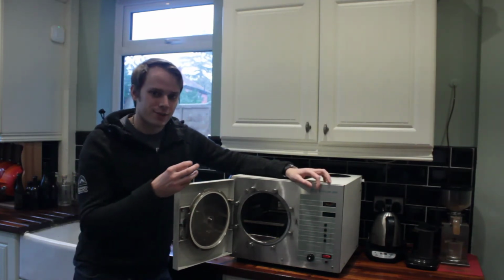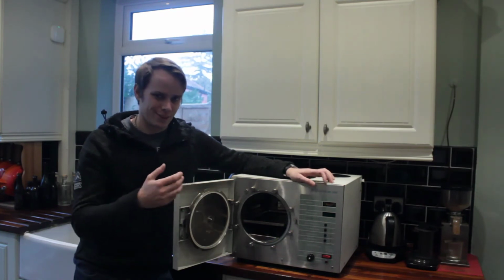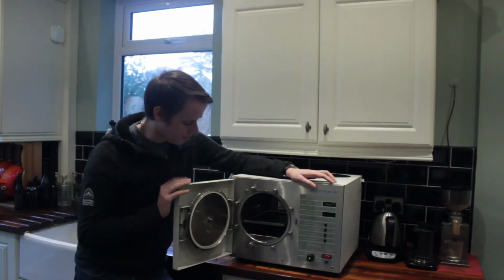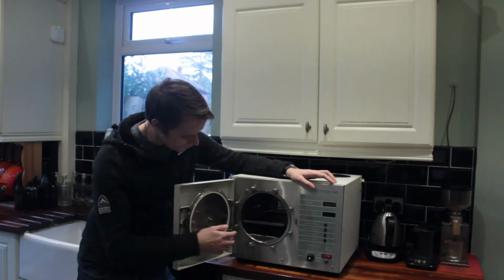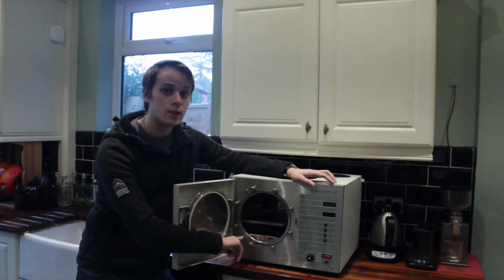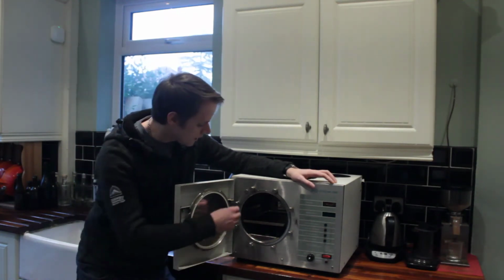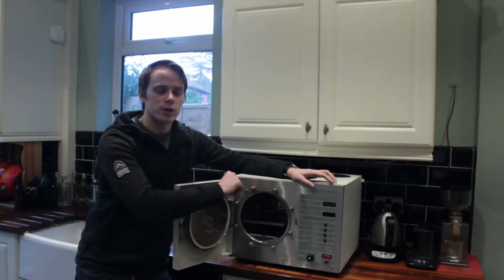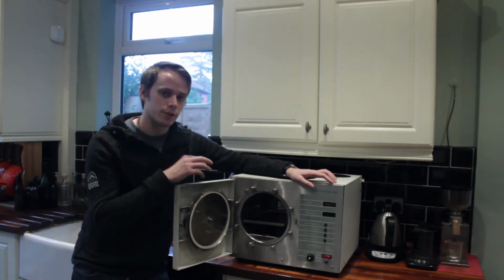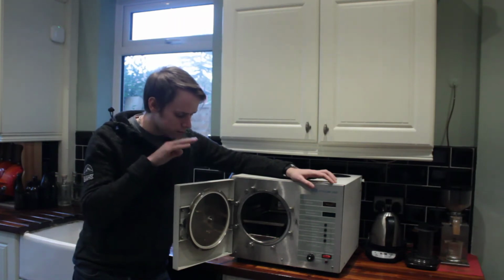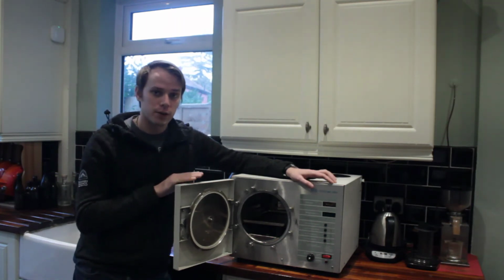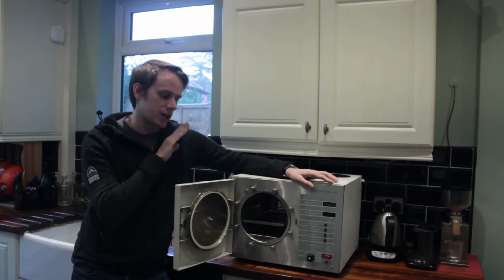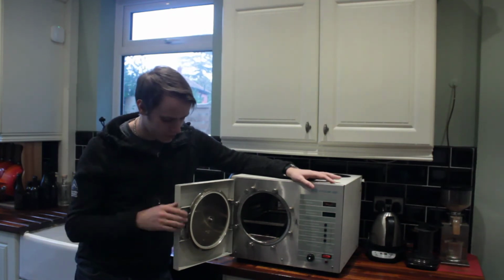That allows us to get into the pressure vessel, but also allows us to get those high pressures and high temperatures. We've also got a little safety switch here which detects when the door is locked, and there's a little plunger here which is activated by the pressure in the chamber itself, and that will lock the door so that you cannot open it while there is pressure within the vessel. That keeps us safe.